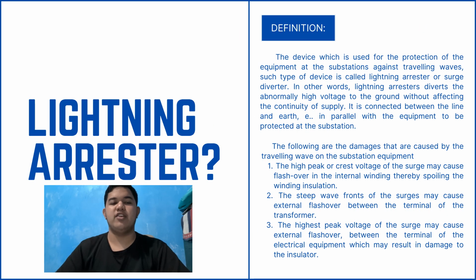What is a lightning arrestor? By definition, a lightning arrestor, also known as a surge diverter, is a protective device used in electrical substations. Its main job is to shield equipment from traveling waves caused by lightning or switching surges. In simpler terms, it diverts abnormally high voltages safely to the ground, keeping the power supply running smoothly and preventing equipment damage. It's usually connected between the line and the earth, in parallel with the equipment that needs protection.